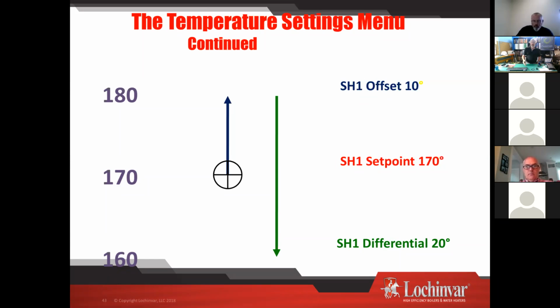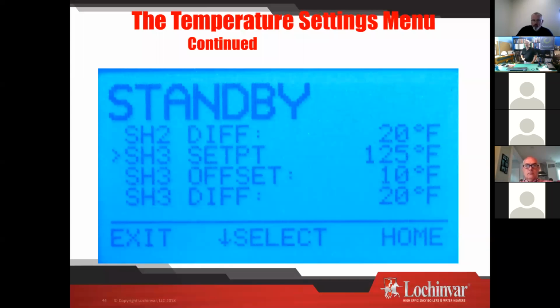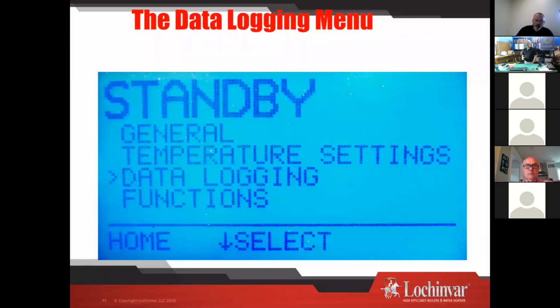If you're operating a heat pump loop, when we are in heat pump loops, a lot of times we have a 3-degree offset and a 6-degree differential. Now we got a really tight window for that boiler to operate in, because those type of systems don't want to see big swings. So they can all be set up differently, and it's always customizable for whatever you got. All right. You said there's 3 of those. So it's 1, 2, and 3 that you'll see within there.